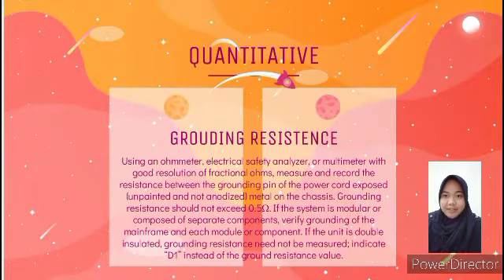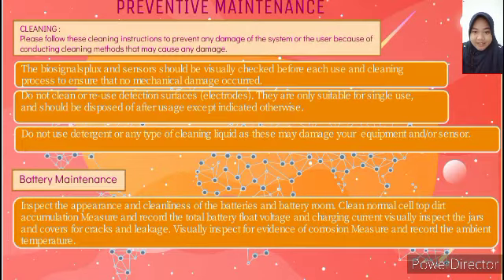Quantitative grounding resistance: using an ohmmeter, electrical circuit analyzer and multimeter with good resolution of fractional ohms, measure and record the resistance between the grounding pin of the power cord and the exposed, unpainted and not anodized metal of the case. Preventive maintenance cleaning: please follow this cleaning instruction to prevent any damage to the system or the user because of a cleaning method that may cause damage.